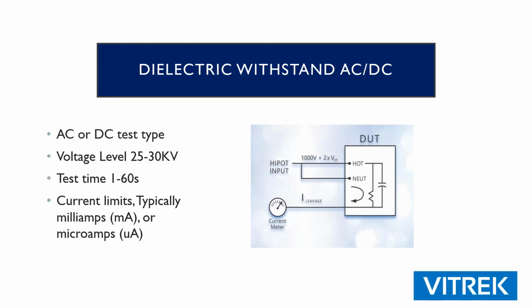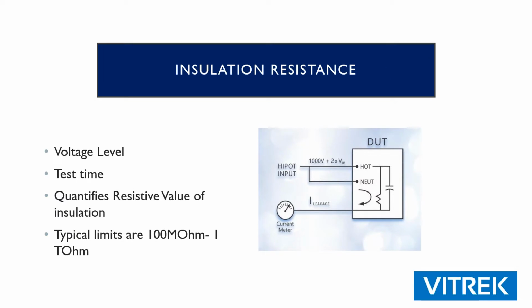We have customers that are doing a lot of long-term testing with the switch in the 950 to really see what's going to happen to their products in 5-6 months, even a year. So an IR test is really the same thing electrically. The difference is that we're going to quantify the value of the insulation in ohms, where on the HIPOT test, we're typically going to display the current in amps. At the end of the day, they're very similar.